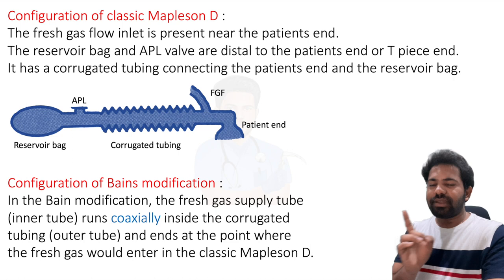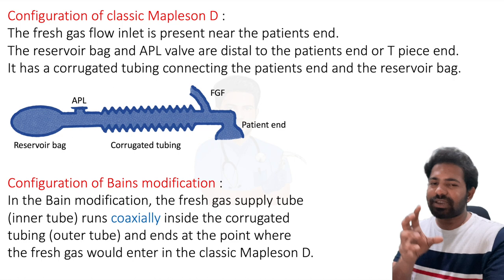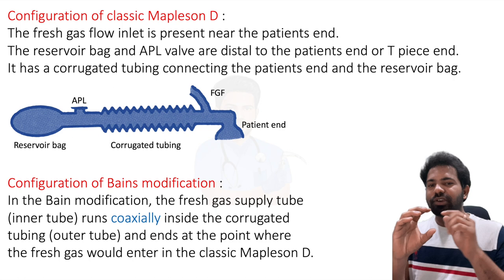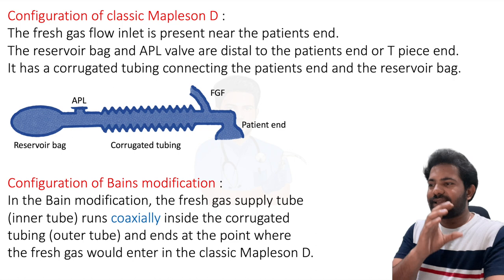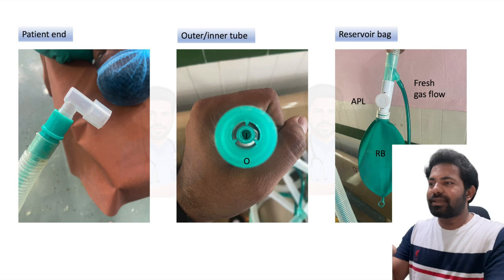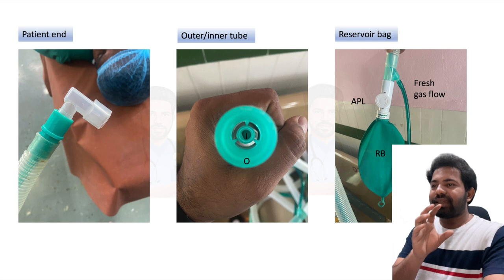In Bain's modification of the Mapleson D, the fresh gas supply tube — the inner tube — runs coaxially inside the corrugated tubing: a tube-within-a-tube model. The outer tube is corrugated and transparent, and the inner tube runs through it, delivering fresh gas to the patient's end. You can see the T-piece at the patient's end, and the outer tube containing the coaxial inner tube.